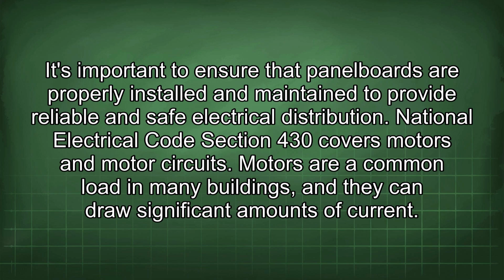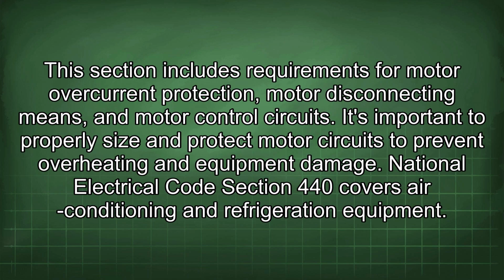National Electrical Code Section 430 covers motors and motor circuits. Motors are a common load in many buildings, and they can draw significant amounts of current. This section includes requirements for motor overcurrent protection, motor disconnecting means, and motor control circuits. It's important to properly size and protect motor circuits to prevent overheating and equipment damage.